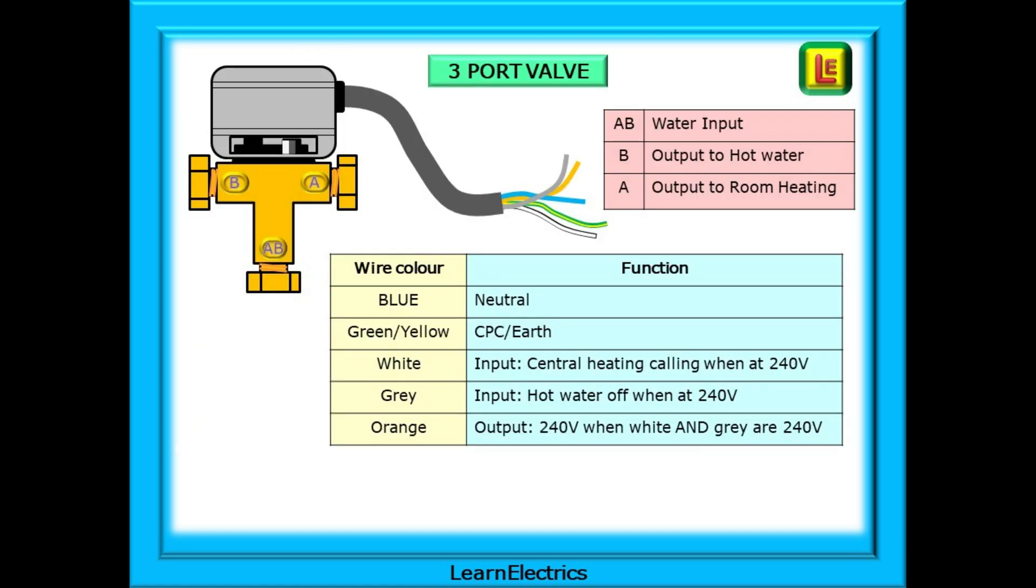The three port valve has a common input port marked AB. In a no power switched off state, an internal spring will hold the valve in the port B open position, and it will be useful to remember this when we look at the circuit operation. Port B output is for the hot water heating and the port A output is for the central heating. And of course we can have the valve set so that both port A and port B are open at the same time.